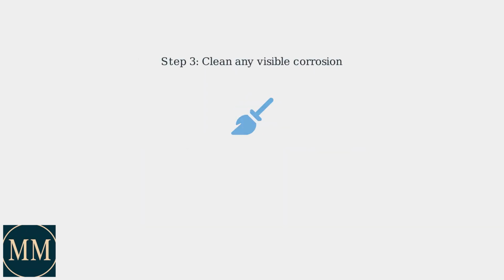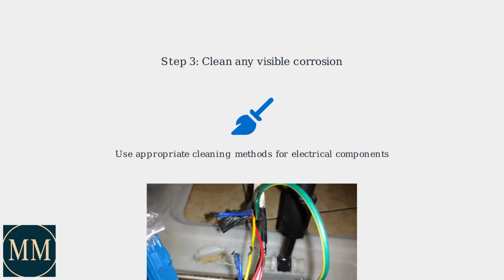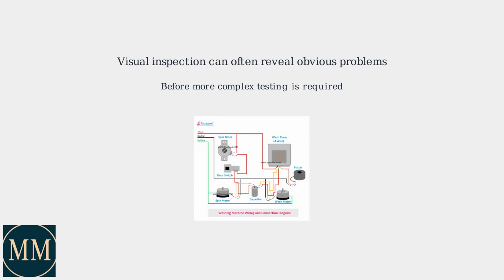Clean any visible corrosion from the sensor or wiring. This can restore proper electrical connections and prevent signal interference. A thorough visual inspection can often reveal obvious problems like damaged wires or faulty connections. This saves time by identifying issues before more complex testing is needed.